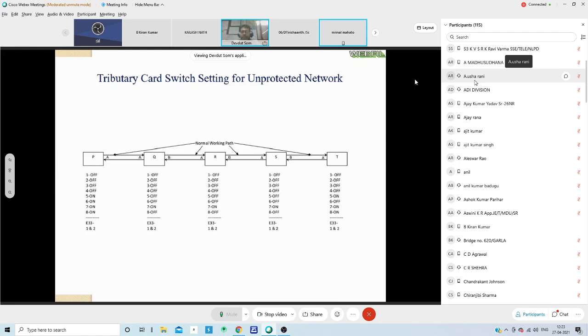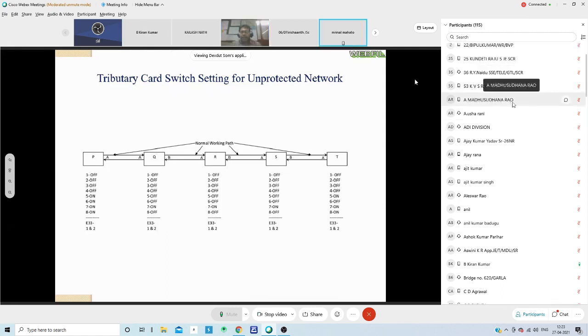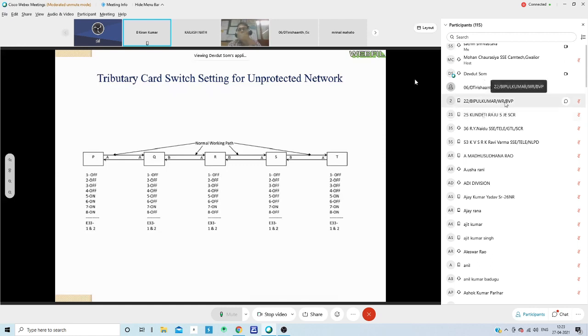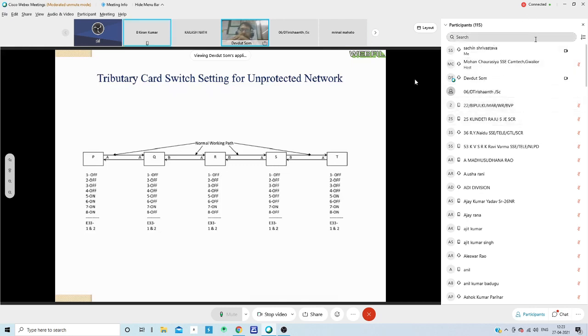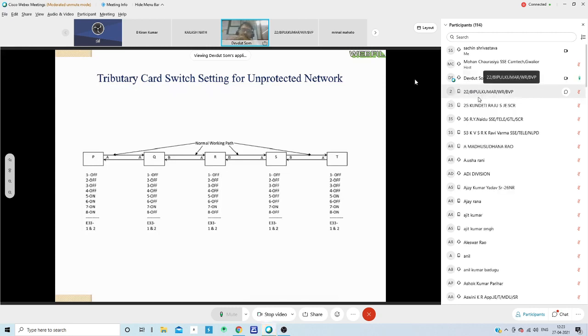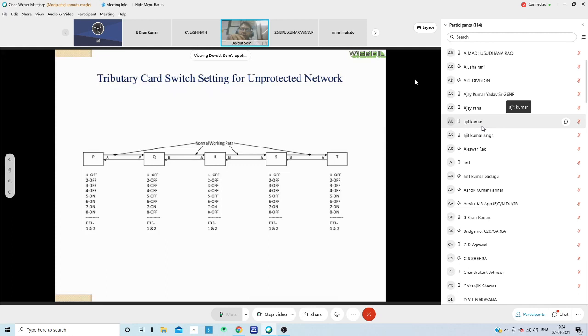I forgot to tell you one thing: at the point where we have given the port, there are 3 parallel connections given from the same MUX point for the control channel, all in cable. That should not be done. In that case, you should use a bridge circuit or a hybrid circuit, which is better because it allows you to match the impedance, since the loop resistance matters. You should not attach 3 parallel lines in a forward circuit; you should use a hybrid or bridge circuit to match the impedance.